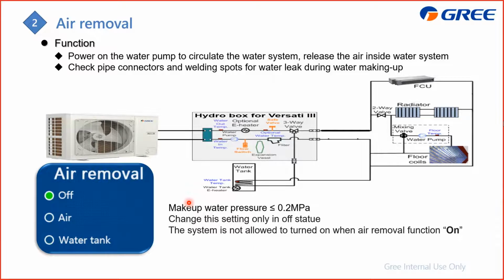After you install the water system, the next step is air removal, which is to drain out the air trapped in the water system. For the system, we just make the water pump operate. Inside it, you need to choose the air removal function on the controller. The controller will ask you which part you need to do the air removal for: the air conditioner, meaning the FCU and the floor coil, or the water tank, which is this part.